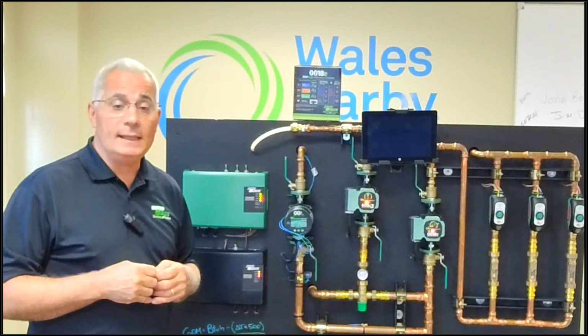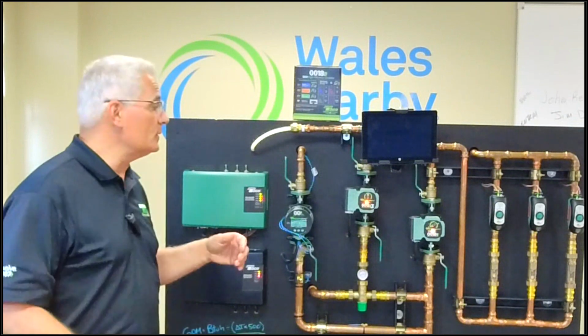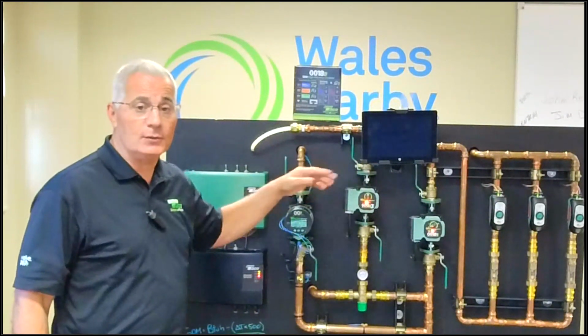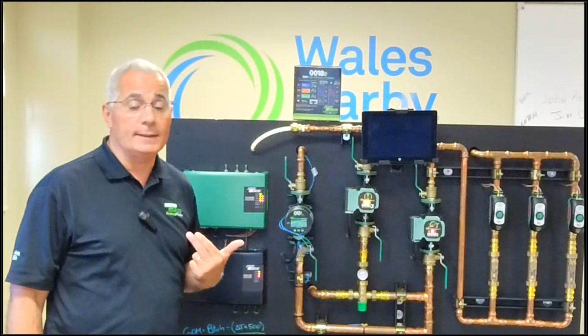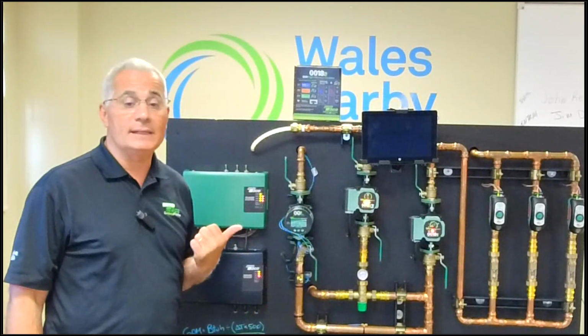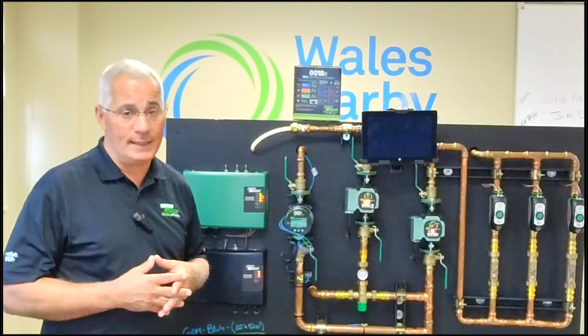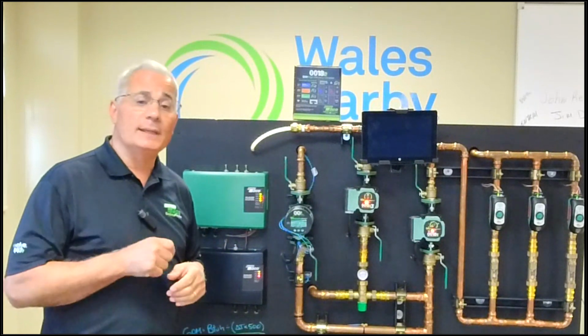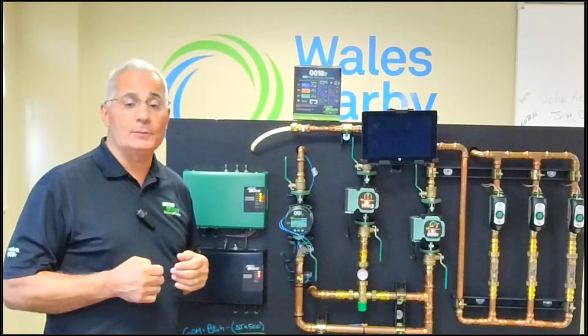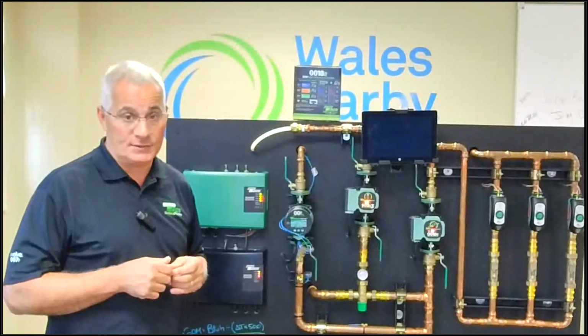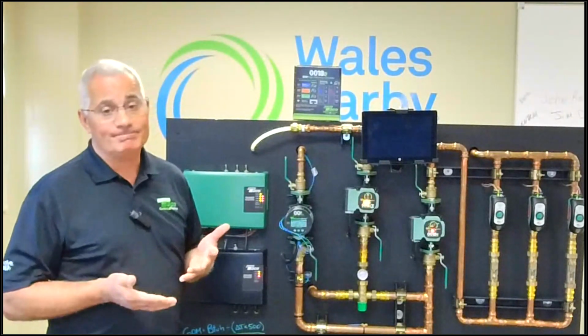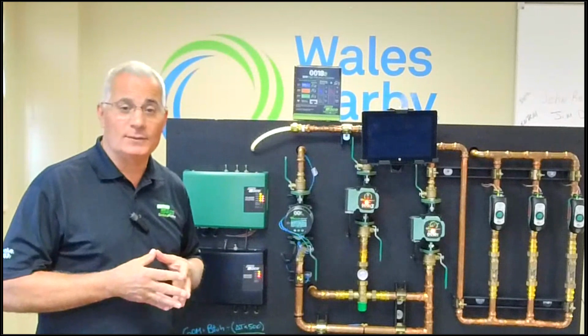So that would mean that if anything on the panel calls and I had this circulator wired there, it would come on whether that radiant zone needs it or not. So I need it to be independent. If it was on the normally open, the only way it would come on would be if I prioritized that zone. So I don't know if I necessarily want to prioritize that zone.